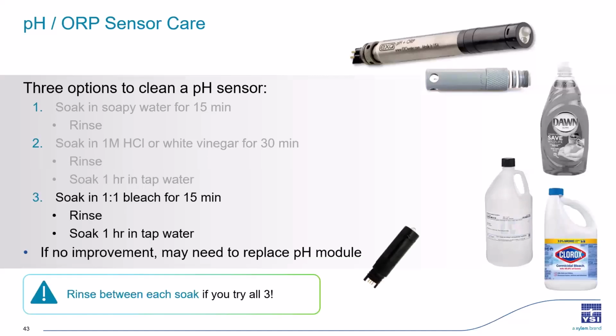If you notice it's taking a long time for your sensor to stabilize when you calibrate, that would be a sign that your reference junction is fouled. Bleach can help draw this out, and it can also help if you have tough fouling on the bulb that won't come off. You can try to soak the sensor tip in a 1-to-1 dilution of bleach to water for 15 minutes and then rinse it off with tap water.